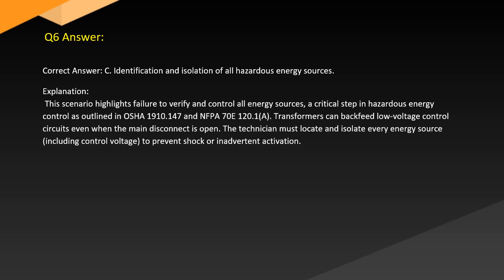Answer. Correct answer: C. Identification and isolation of all hazardous energy sources. Explanation. This scenario highlights failure to verify and control all energy sources, a critical step in hazardous energy control as outlined in OSHA 1910.147 and in NFPA 70E and 120.1.